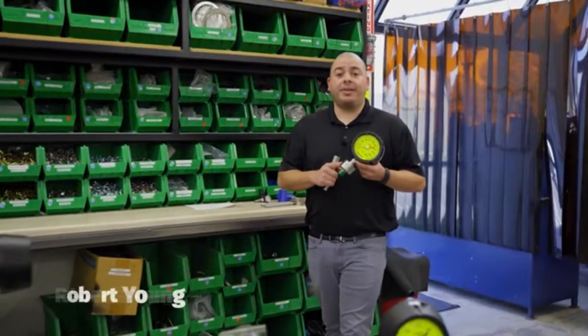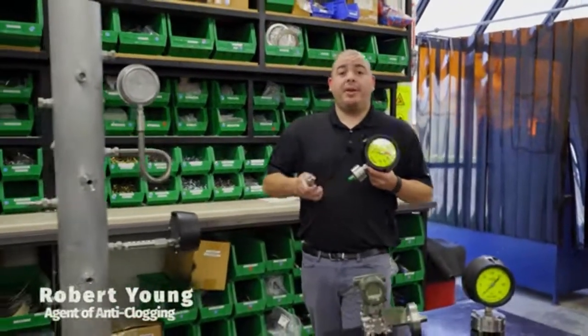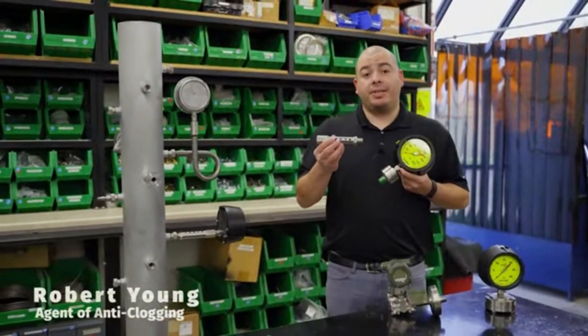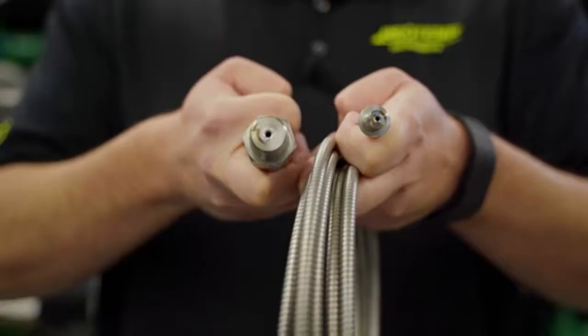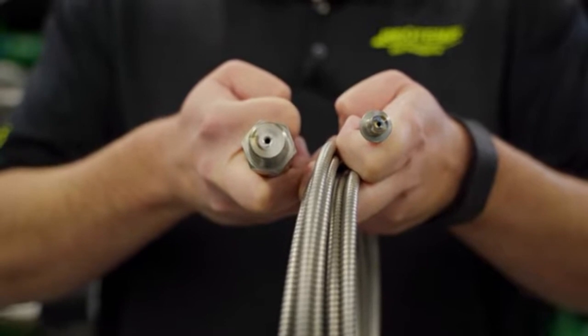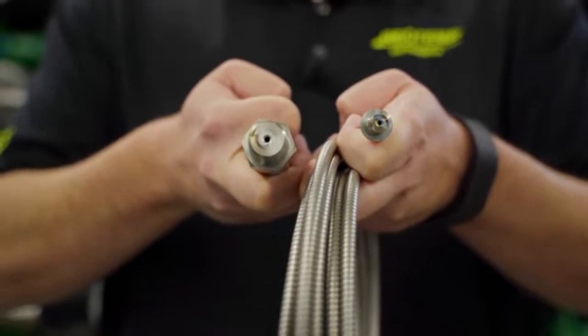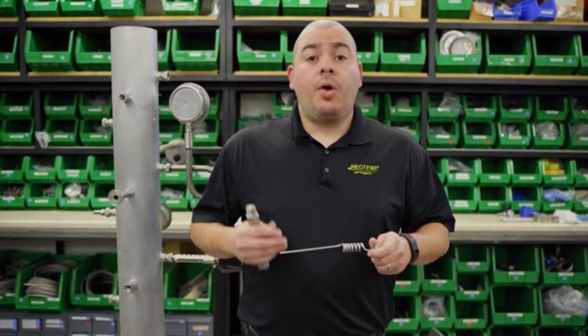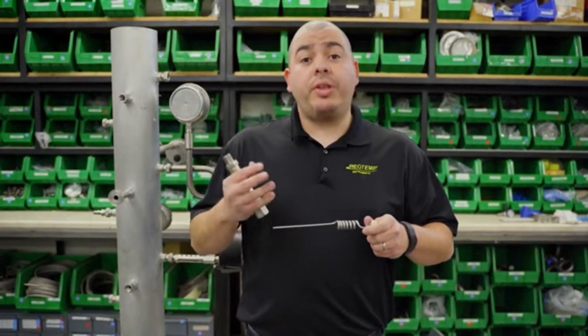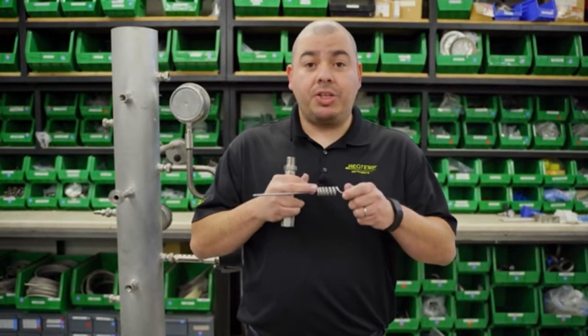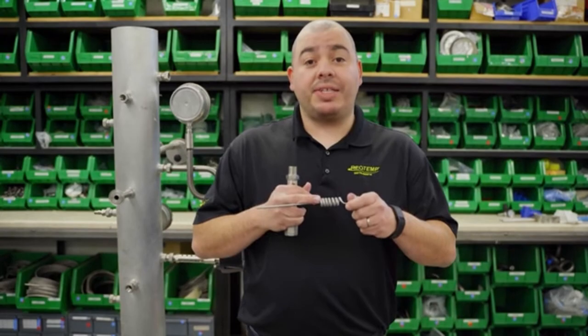The diaphragm seal isolates the process fluid from entering into these cooling elements. So consider using them when the fluid being measured gets thicker when cooled and may clog in the small orifice of the capillary or cooling tower, or for freeze protection when there's concern that water may condense within the tubing itself and risk freezing.